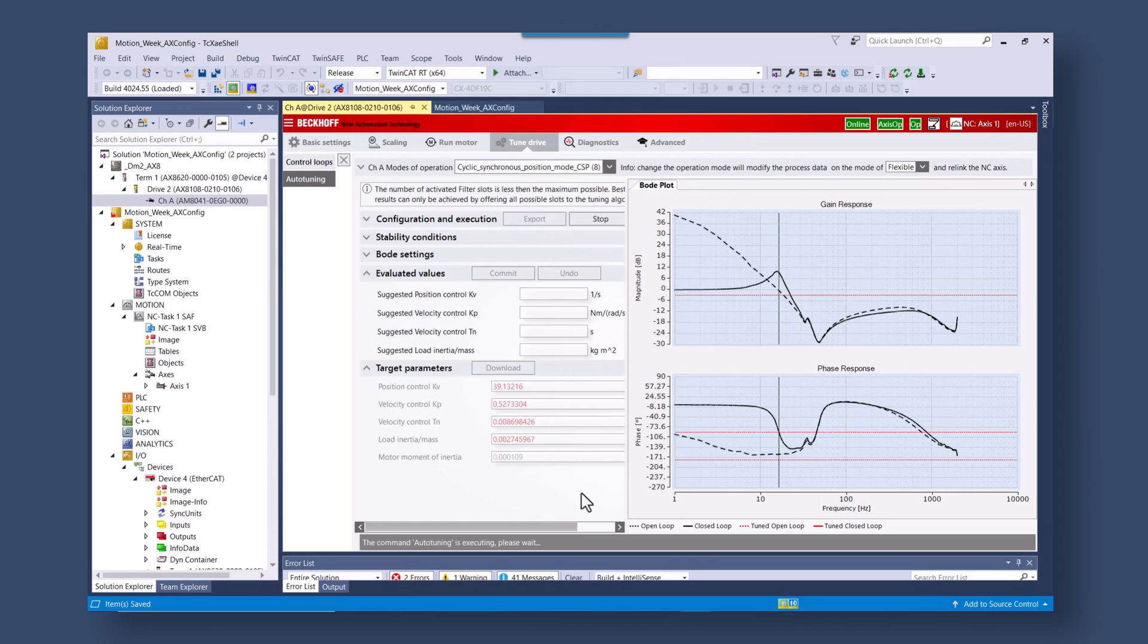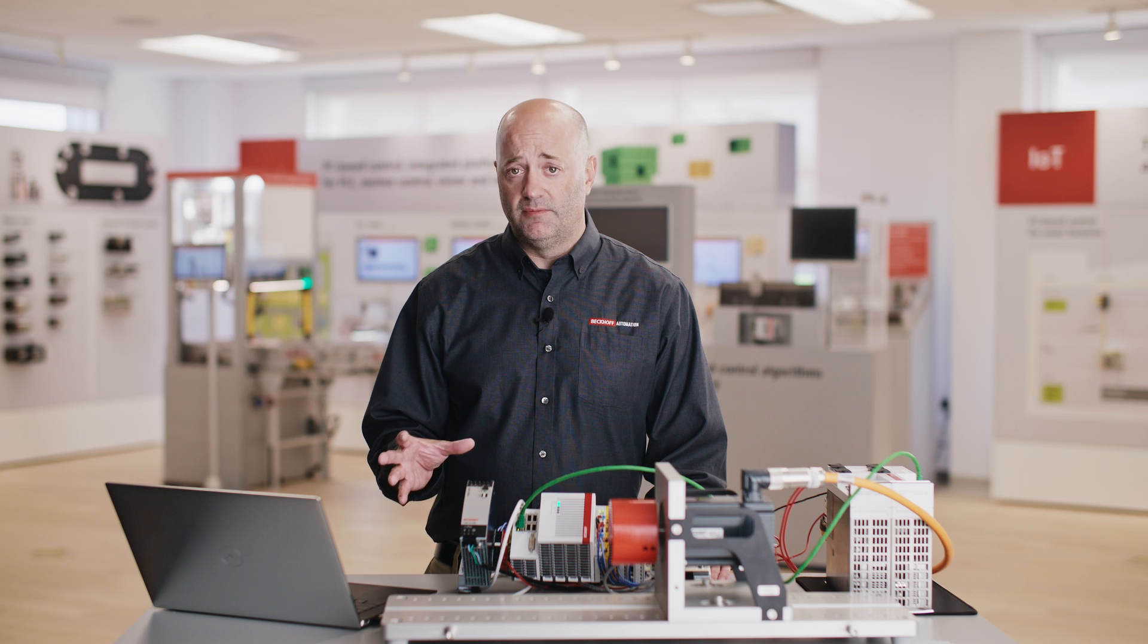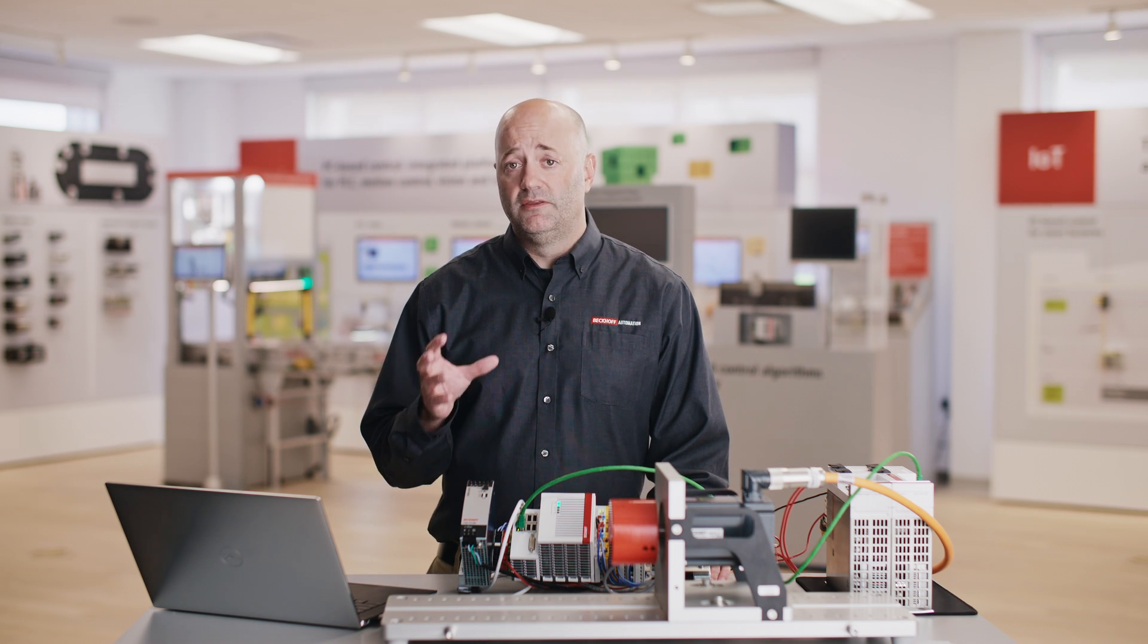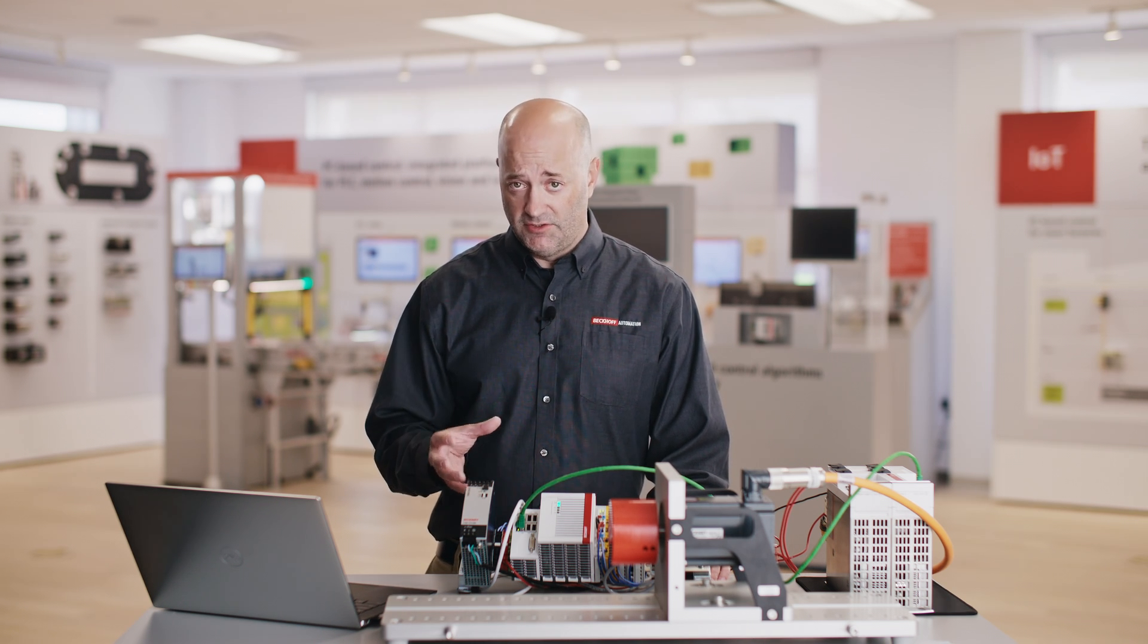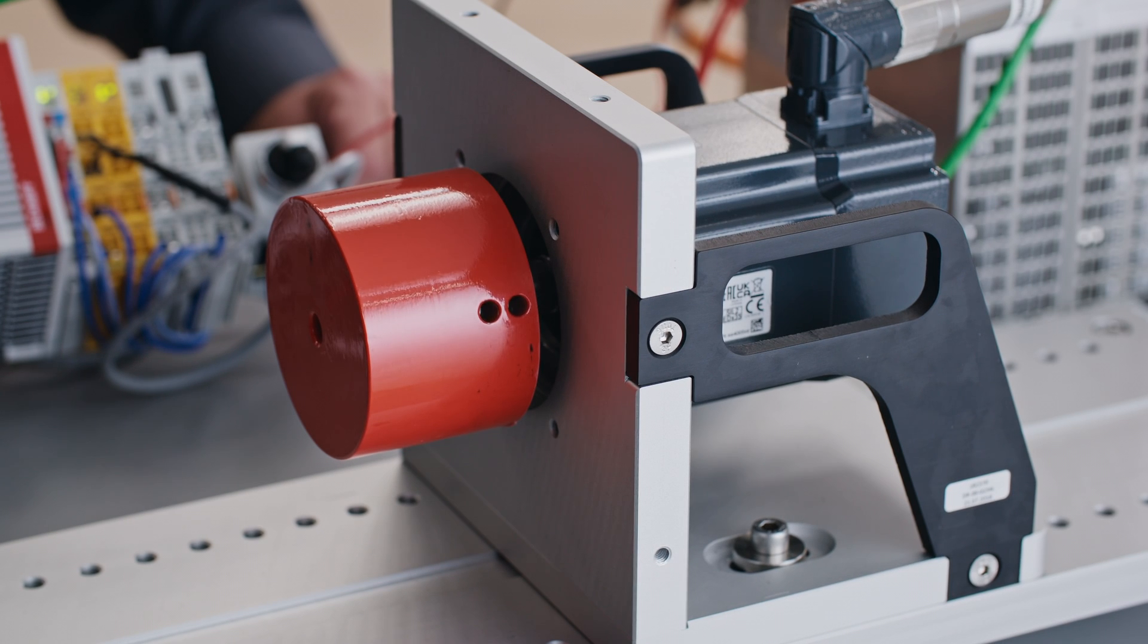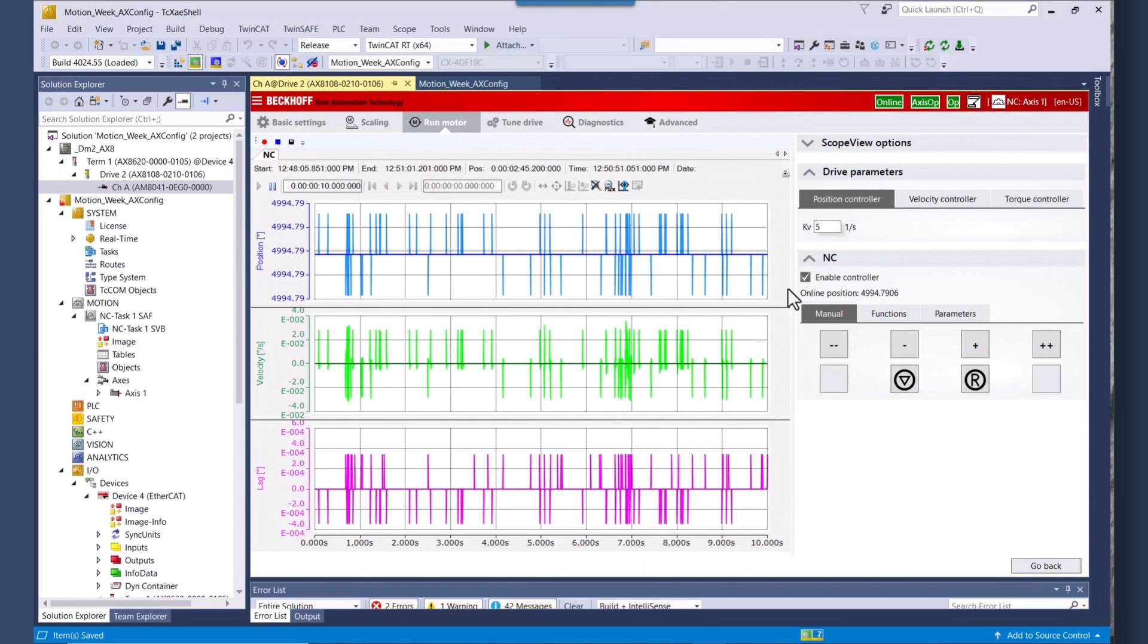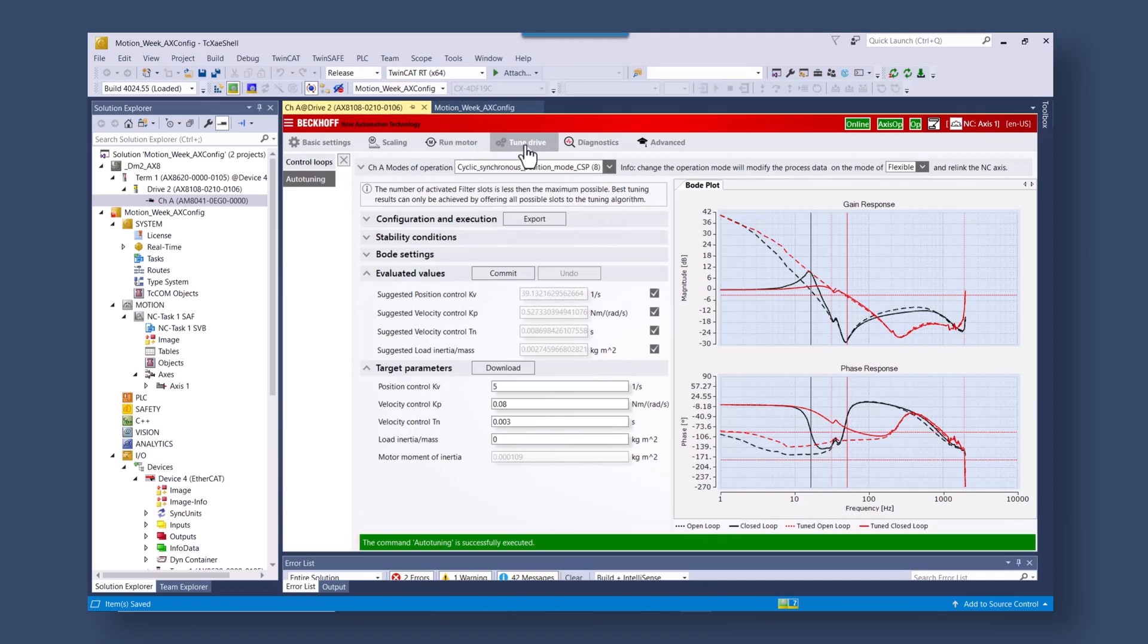So the next step in auto tuning is actually starting the auto tuning process. Note that when you execute the auto tuning feature, the axis is going to oscillate. So you're going to see motion in the axis. This is going to give us the oscillation that we need to analyze the data. Take care when you execute the auto tuning because the motion is going to happen on the axis.